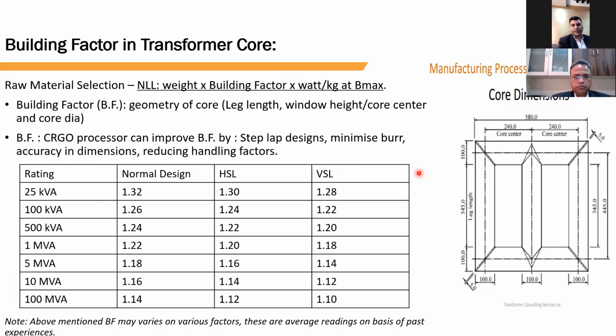Let's take an example of 25 kVA: in normal design, building factor will be 32%. If modified with horizontal step lap design, HSL, it improves by 2%. Further modified with vertical step lap, another 2% advantage is there. So building factor can be improved in terms of CRGO design also. This is the tabulated form of building factor with respect to different transformer ratings.